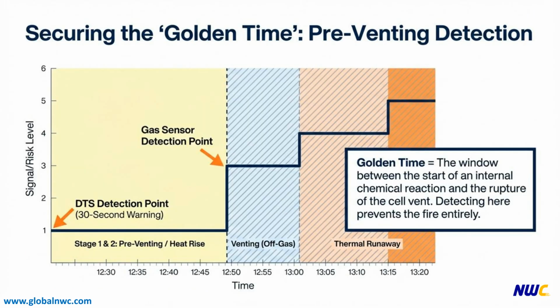Preventing fire propagation in ESS and EV battery systems depends on detecting abnormal conditions within the golden time before off-gas generation occurs. DTS technology provides early warnings more than 30 seconds in advance, identifying thermal anomalies at stage 1 and stage 2, well before gas sensors can respond. By enabling intervention at this early stage, the system can fundamentally prevent thermal runaway from developing. This level of precise early detection is a critical technology for preventing large-scale fire incidents and maximizing overall system reliability.